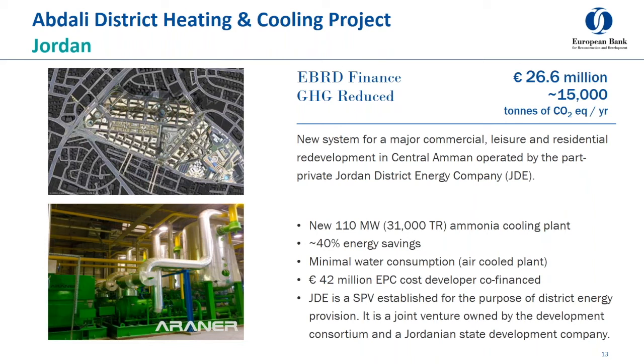And there was also a large cost associated with network installation, but this was built by the developers in the early stages of the project. So in addition to the interesting model, this was an exciting project that contained some cool technical innovations, such as the largest thermal store in the Middle East at the time of construction, and the use of air-cooled condensers on a large-scale ammonia installation. Oh, and at the time, it was also the first district cooling network in Jordan, I believe still the only.